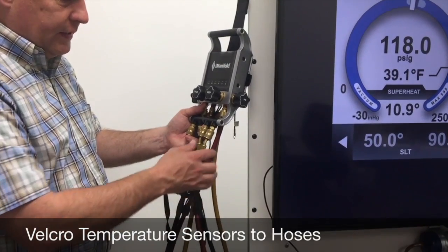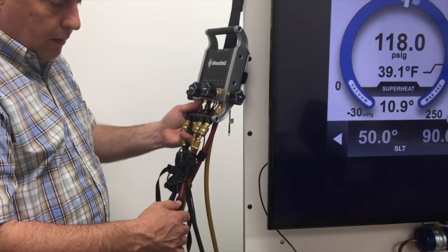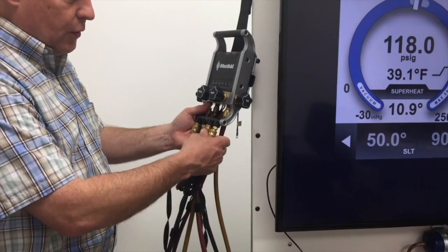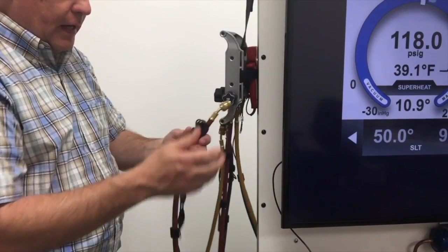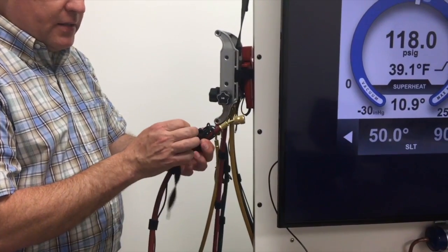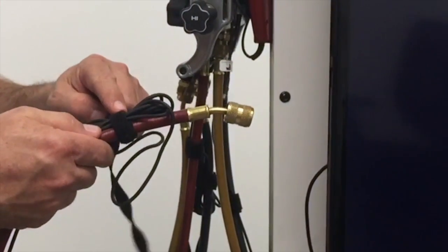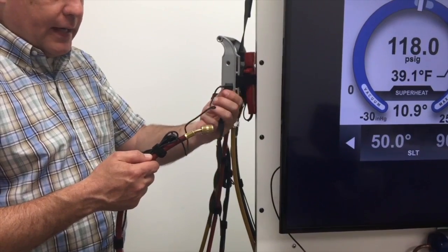All right, so the first thing you'll notice is when I set up my Imanifold, I Velcro my temperature sensors right to my hoses. The reason I do that is so when I take off this hose set, if I have the high side probe, I also have the high side sensor. I Velcroed the bulk of the excess wire right to the hose here, and I have just enough that I can work with.